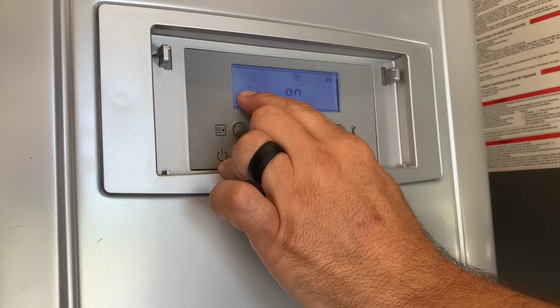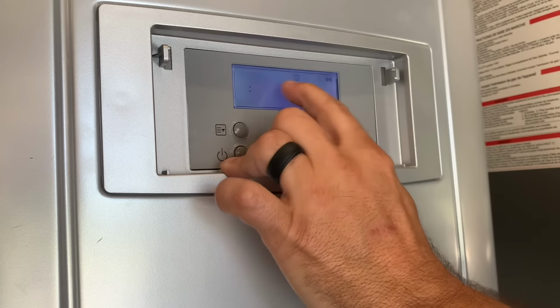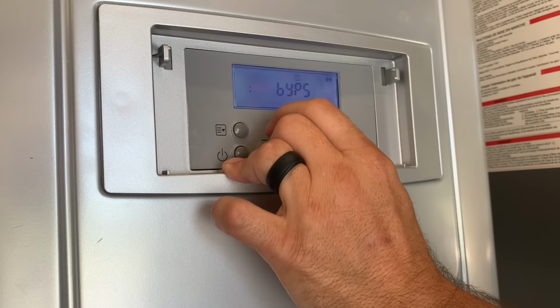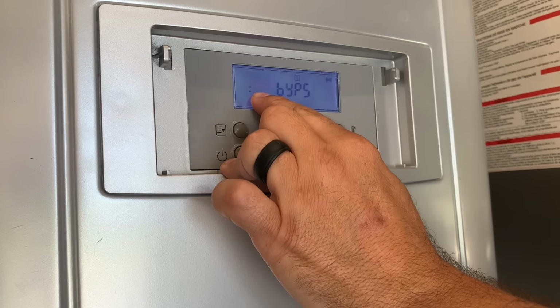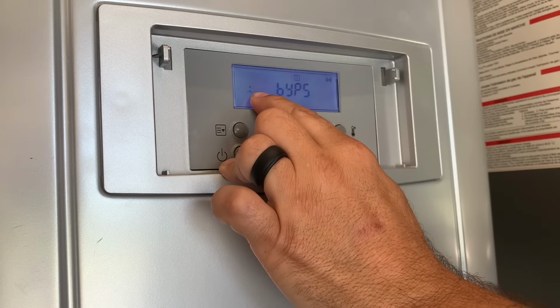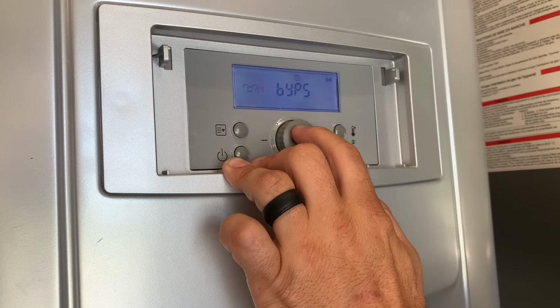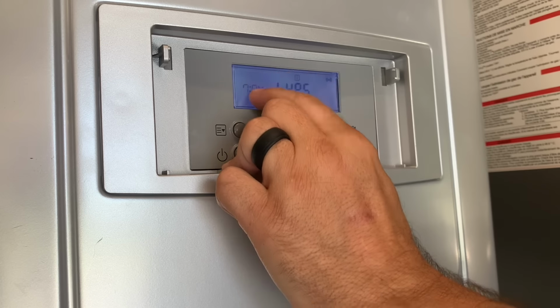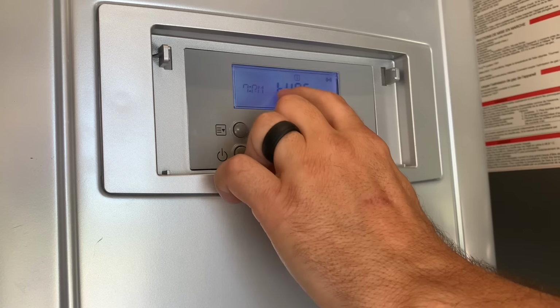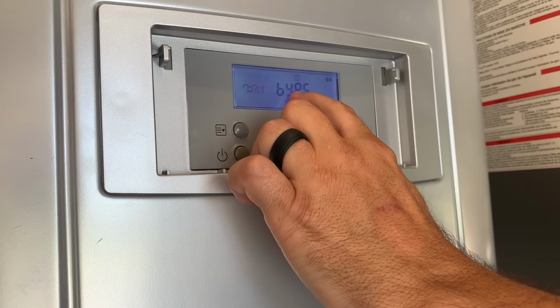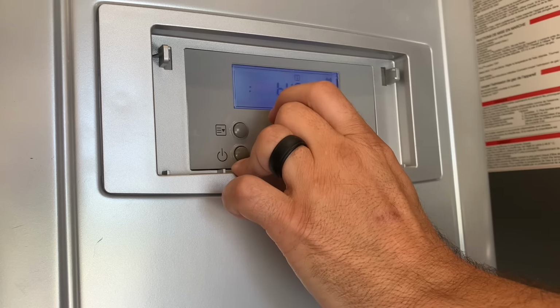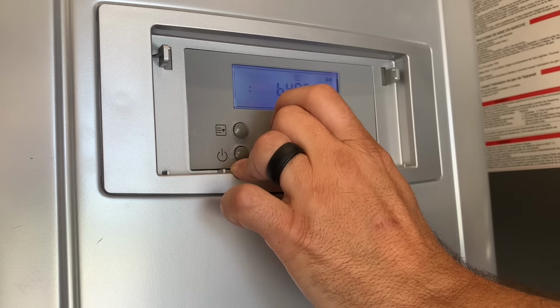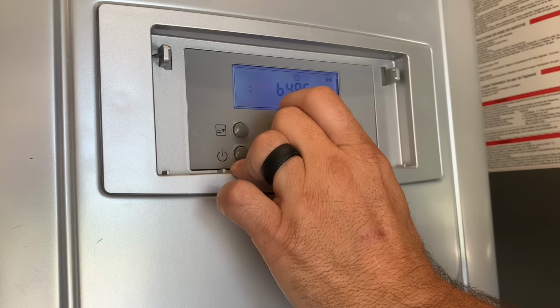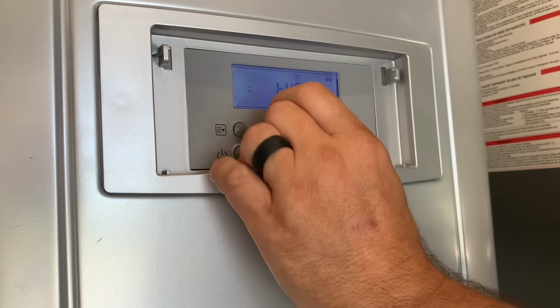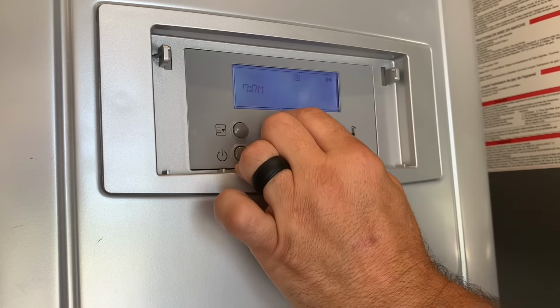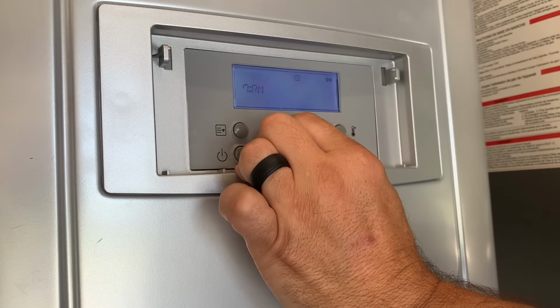once you have your pump recirculation on, you can move to 7RM. This will tell the heater what recirculation mode you want to be in. 6RC must be on to access this. Right now it is in bypass. The bypass is a bypass that will be installed on your plumbing at the furthest fixture. If you do not have a dedicated return line, you can start at the top here.